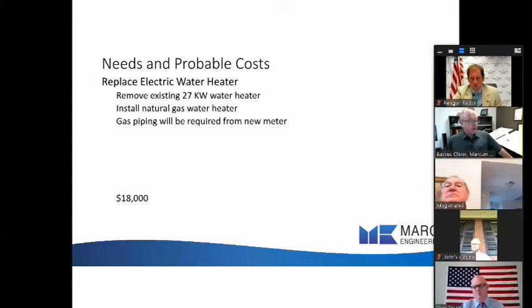This is something that's optional. I would consider replacing your electric water heater on the ground level. It's a 27 kW water heater. Now that you would have natural gas in the building, you could easily change that to a gas water heater. And we would have to install gas piping just a little differently and over to that area. That would be $18,000 to make that improvement. That will produce an energy savings. The ROI on this, I don't know, but it does have some savings. You could perhaps wait till the water heater is bad, and when you replace it, just change to gas then.